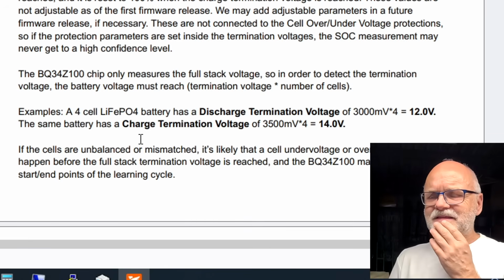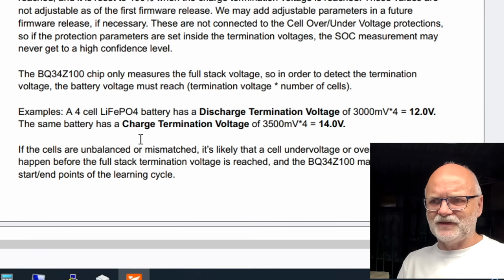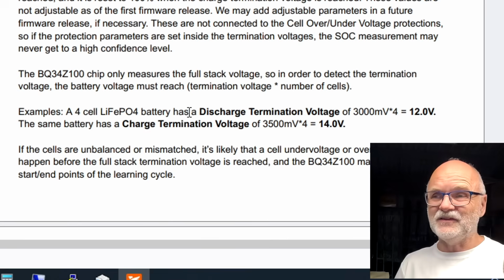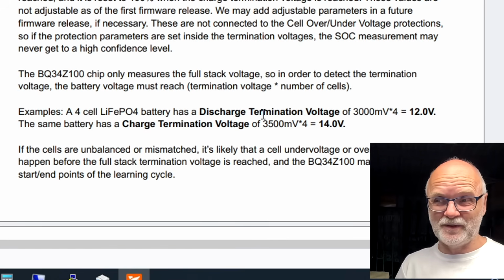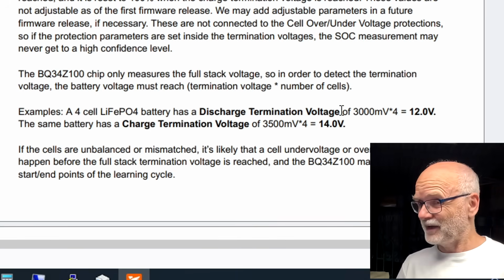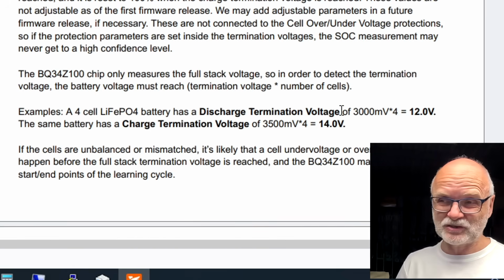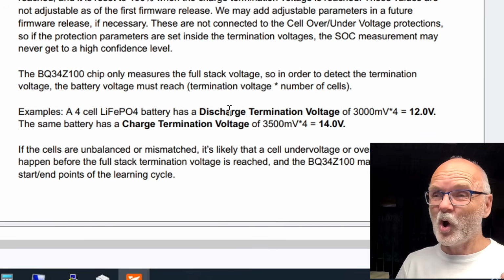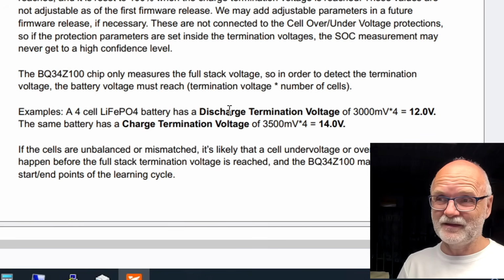So the learning basically between 0% and 100%, it uses the discharge termination voltage. At the beginning I thought this is the over voltage protection, but no, this is a different setting, obviously a different parameter, which we can hopefully set ourselves. And once it reaches the discharge termination voltage, it goes to 0. And once it reaches the charge termination voltage, it goes obviously to 100%.